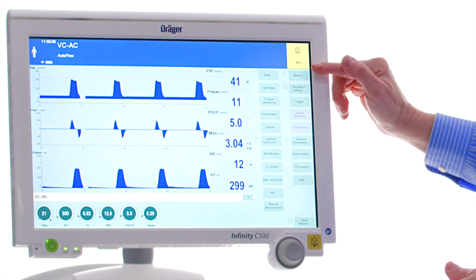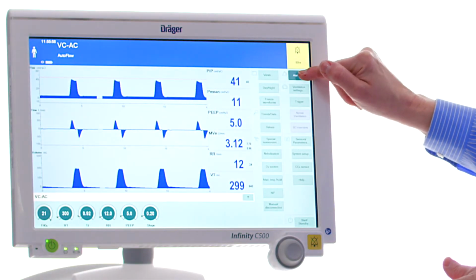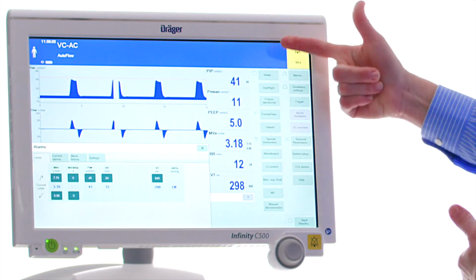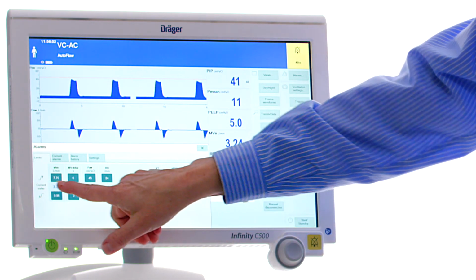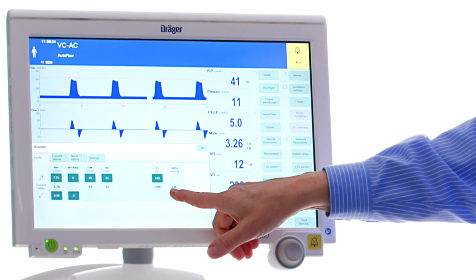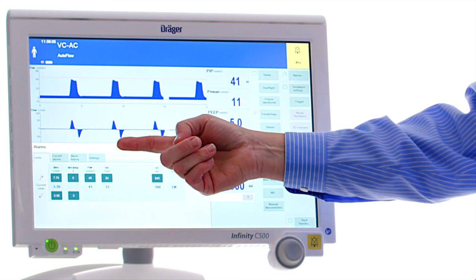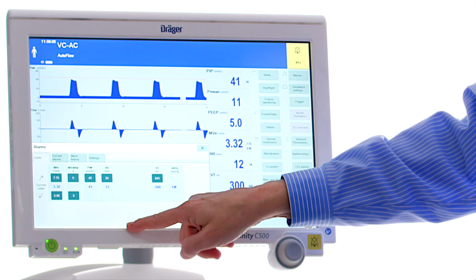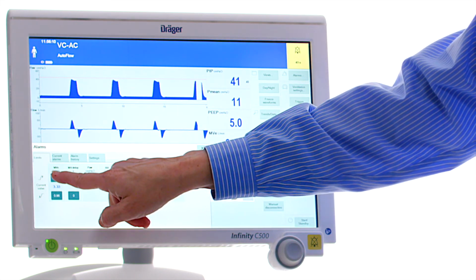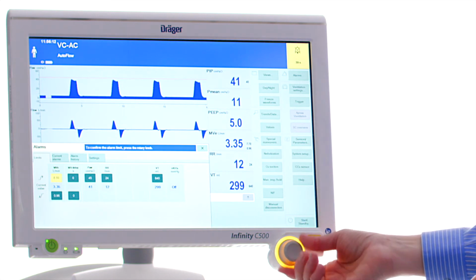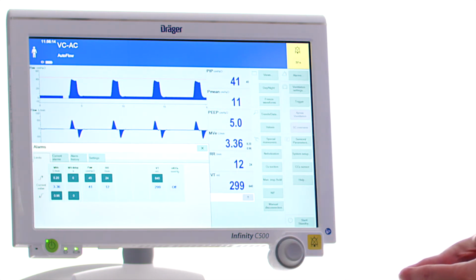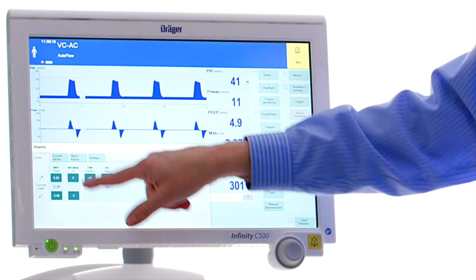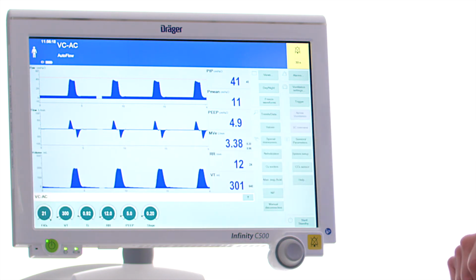To set your patient alarms, you touch the Alarms tab in the upper right-hand corner of the Configure button section. The ventilator will show you what the patient's doing in blue in the middle. Your high alarms are on the top, your low alarms are on the bottom. To make changes, you touch the button, turn, confirm, touch, turn, confirm. To close out that window, touch the X again.